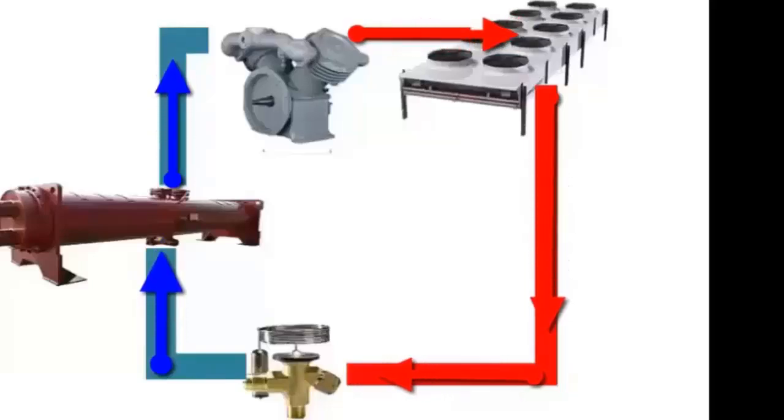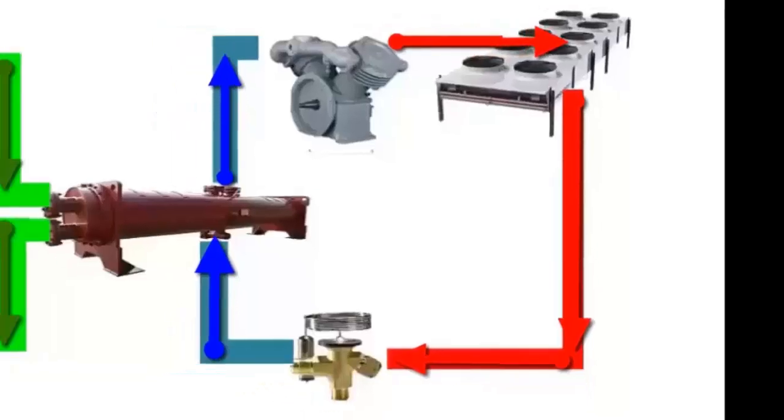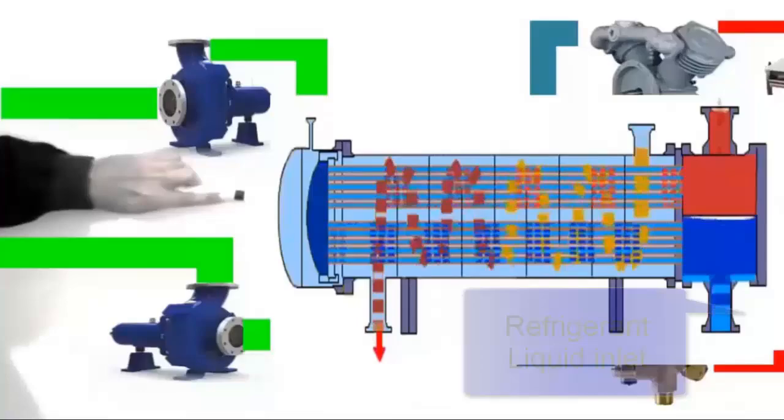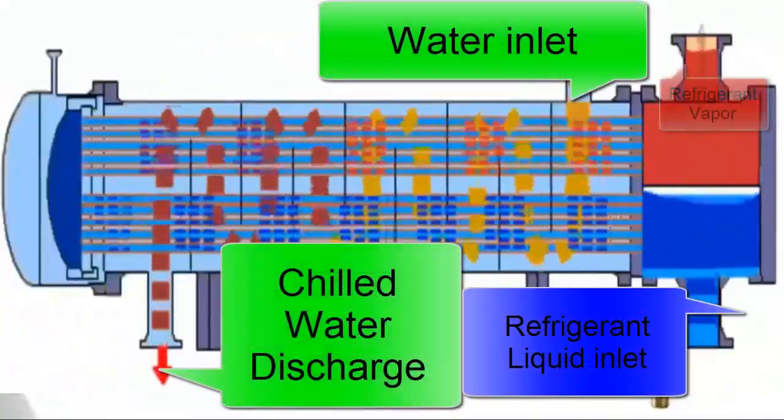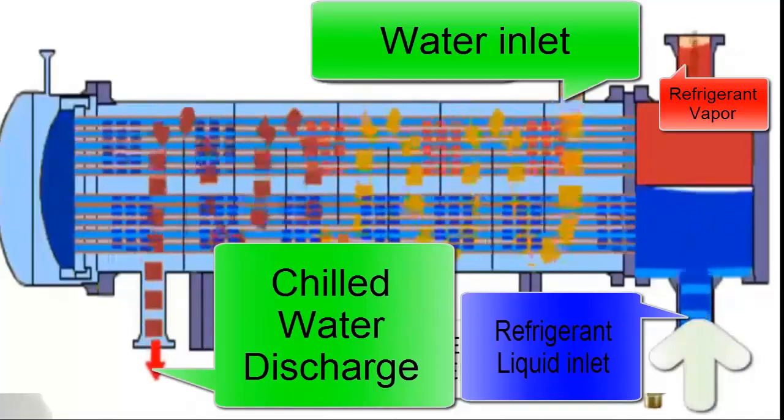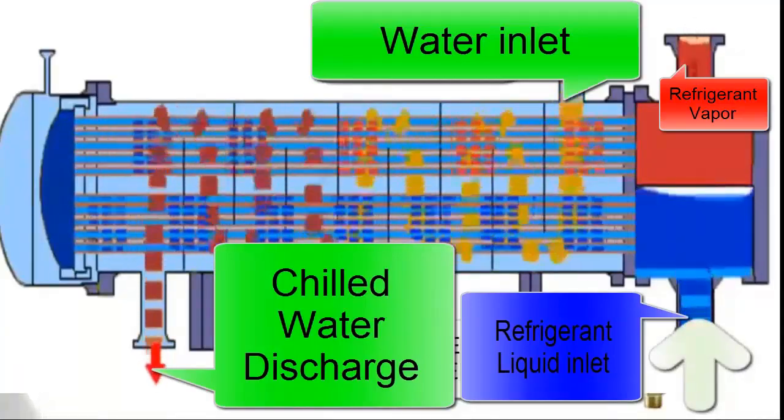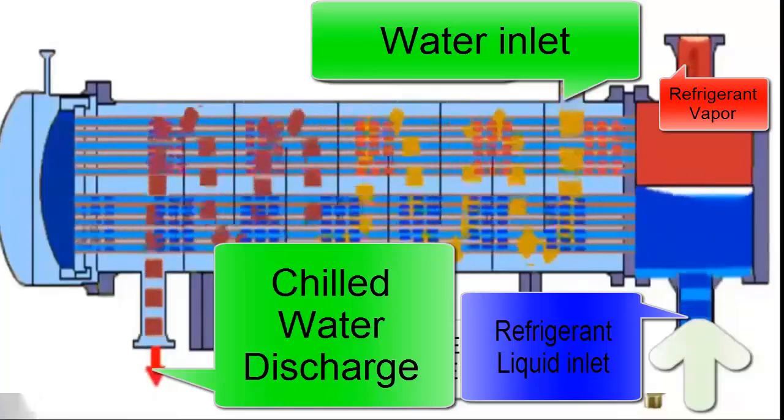The evaporator, on the other hand, is the component where thermal exchange with the water occurs. At this point in the system, the refrigerant, initially in a liquid state, absorbs heat from the water, changing its state to vapor. This state change is a crucial aspect of the refrigeration process, as it is the means by which heat is removed from the water.